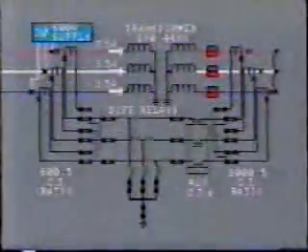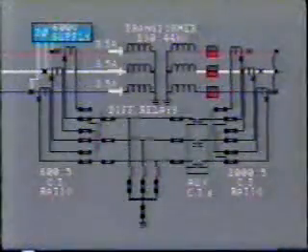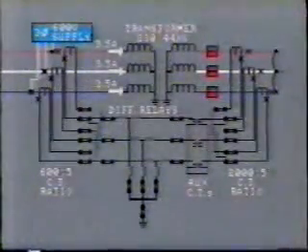For this type of transformer, the test is usually performed by placing a short circuit across the low-voltage side of the transformer and energizing the high-voltage windings from a three-phase low-voltage supply, say 600 volts. This will probably be sufficient to pass a low current through the primary winding, 3.5 amps in this example. By carefully measuring current flow at the appropriate CT links, we can check CT ratio, CT polarities, CT circuit wiring, wiring of auxiliary CTs, wiring of differential relays.